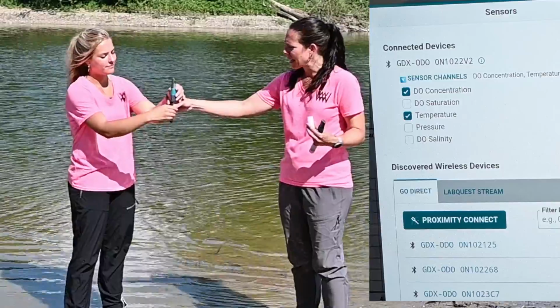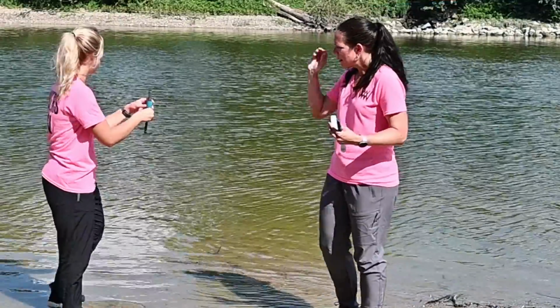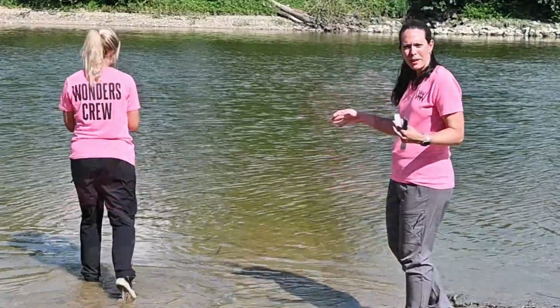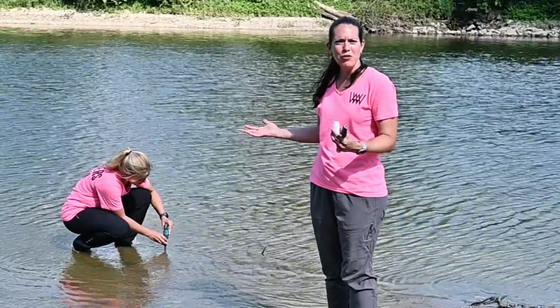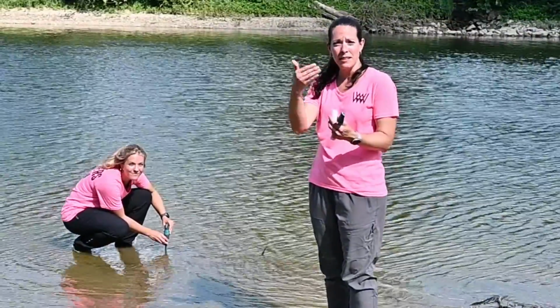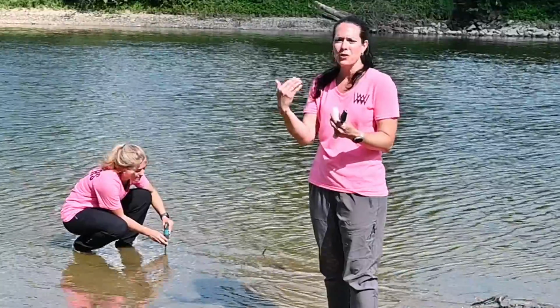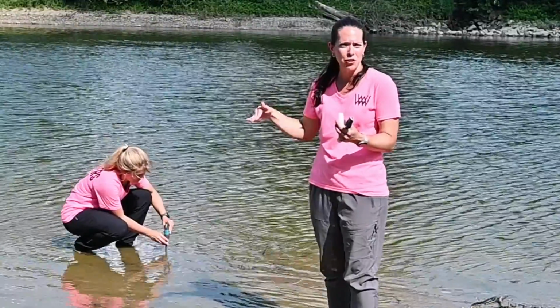Again, we'll hold onto that cap and Claire will demonstrate placing that directly into our water. Claire is taking both the dissolved oxygen reading and a temperature reading. You should start seeing the numbers for those measurements as soon as the sensor is submerged in the water.